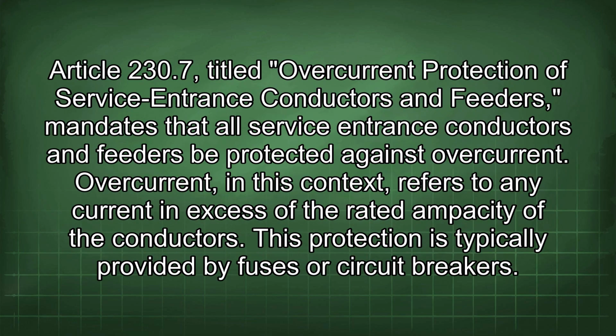Article 230.7, titled Overcurrent Protection of Service Entrance Conductors and Feeders, mandates that all service entrance conductors and feeders be protected against overcurrent. Overcurrent, in this context, refers to any current in excess of the rated ampacity of the conductors. This protection is typically provided by fuses or circuit breakers.